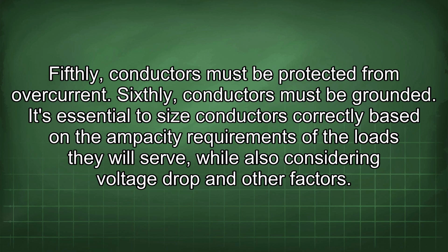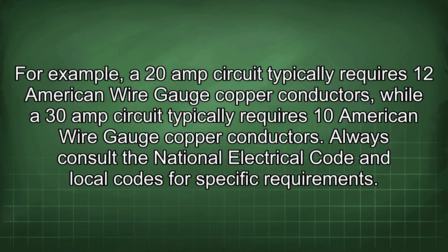It's essential to size conductors correctly based on the ampacity requirements of the loads they will serve, while also considering voltage drop and other factors. For example, a 20 amp circuit typically requires 12 American wire gauge copper conductors, while a 30 amp circuit typically requires 10 American wire gauge copper conductors. Always consult the National Electrical Code and local codes for specific requirements.